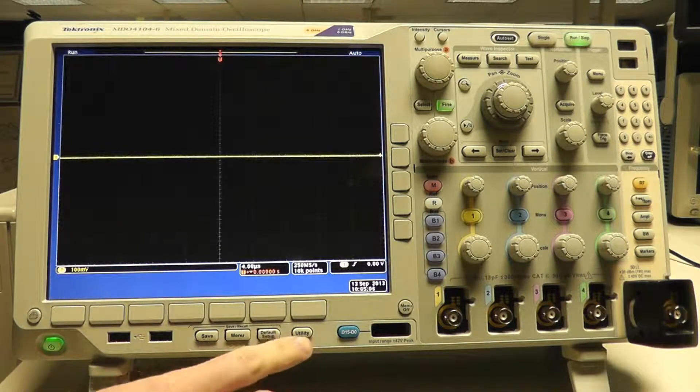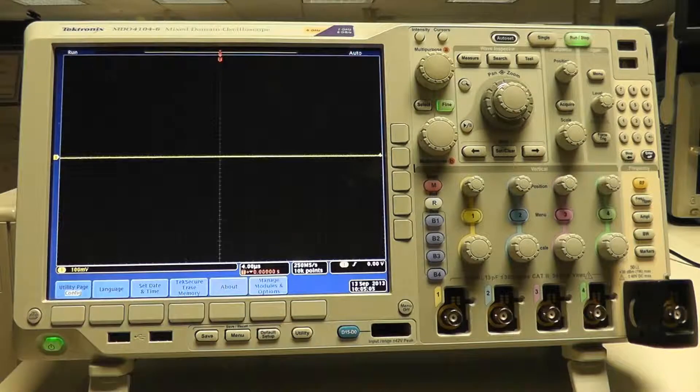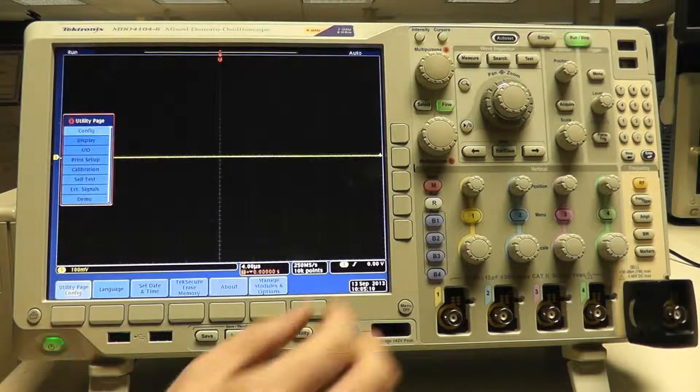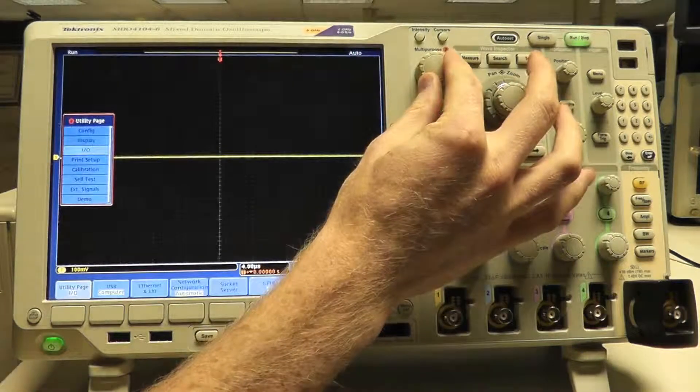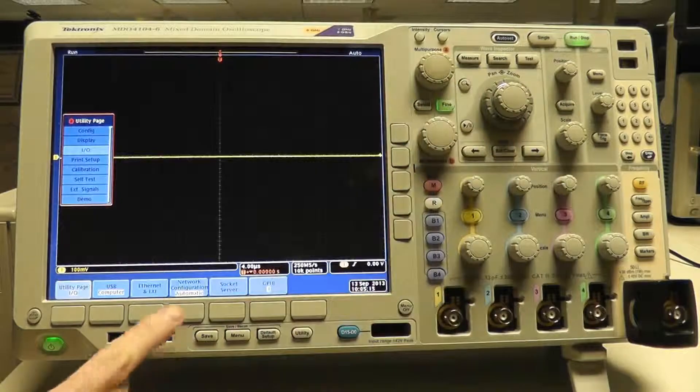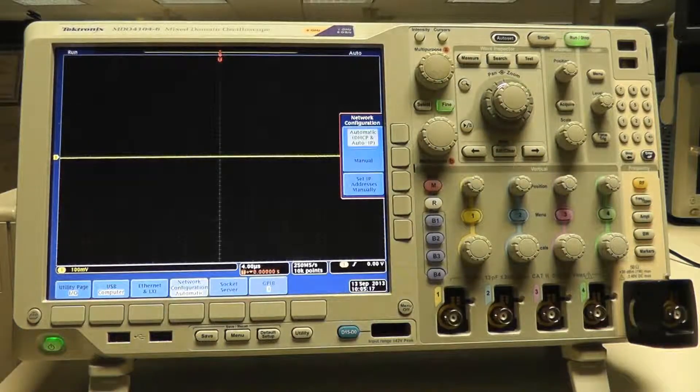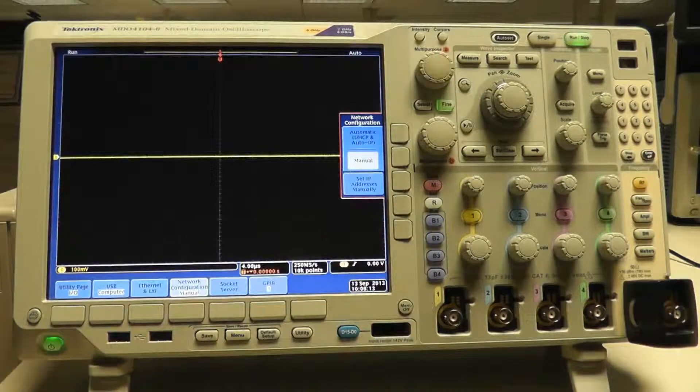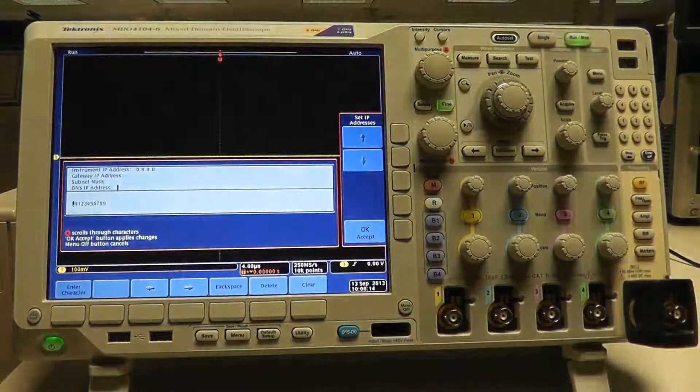This can be seen by going to the Utility menu, scrolling to the I.O. page under the Config menu, selecting Network Configuration, selecting Manual, and selecting Set IP Addresses Manually.